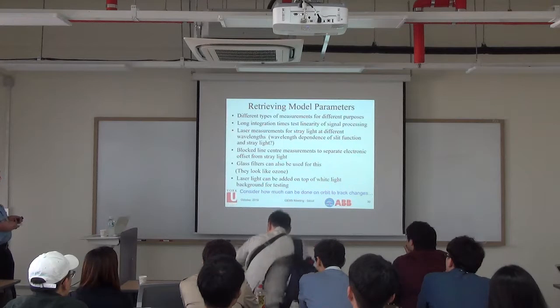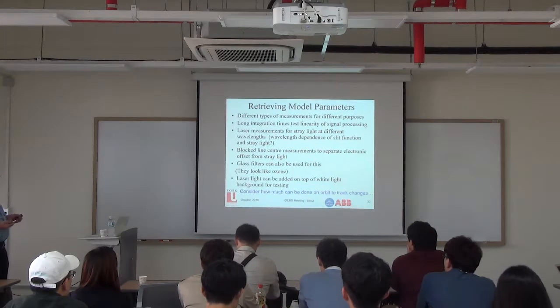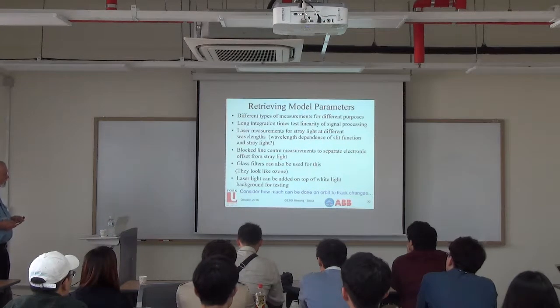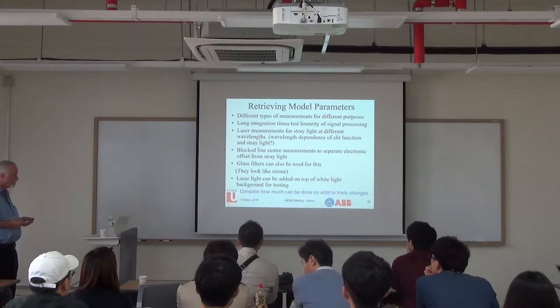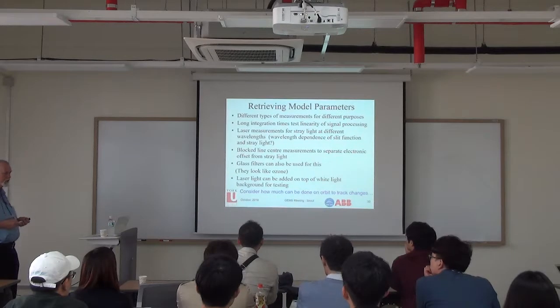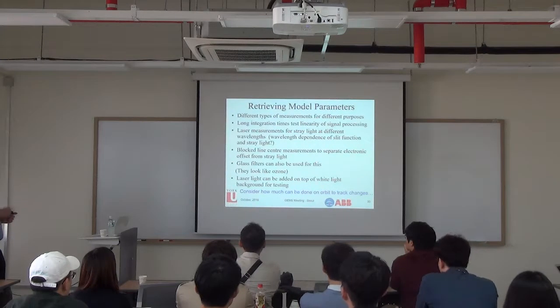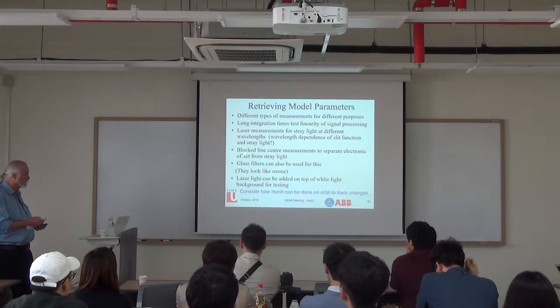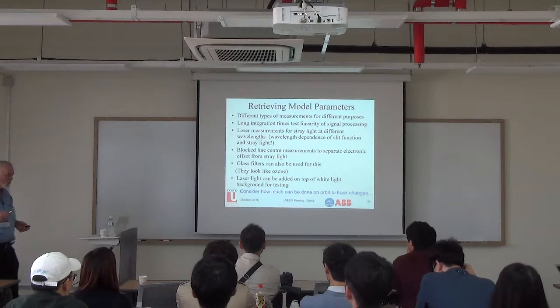One example of calibration strategies in spectral processing: laser measurements allow you to look for stray light as a function of wavelength. The blocked center measurement is useful to separate electronic offsets from stray light. Glass filters are interesting because they mimic ozone by cutting off at short wavelengths—different glass types fall off fairly rapidly at the short-wavelength end. This helps quantify the stray light problem even if it doesn't fix it.